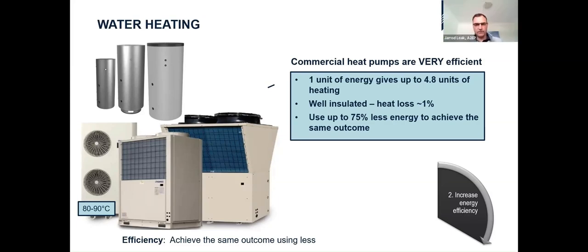It's very important that we do note here as well, you mentioned commercial. Yes, these are commercial heat pumps, and that is quite a difference to what was installed around 2010. Many dairy farms installed heat pumps back then, but they were mainly domestic hot water systems, really not designed for dairy conditions. We understand there are still a lot of farms using those old domestic style ones, and they've got a good 10 or 15 years out of them. But we do see the next generation is this commercial one, much more robust, much better at handling different water qualities and things like that as well.